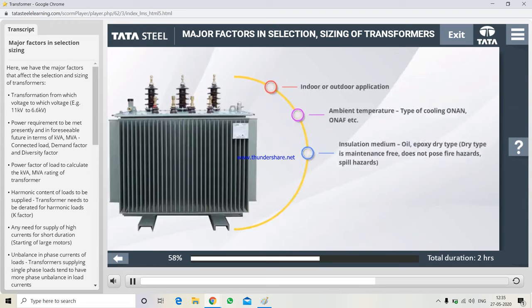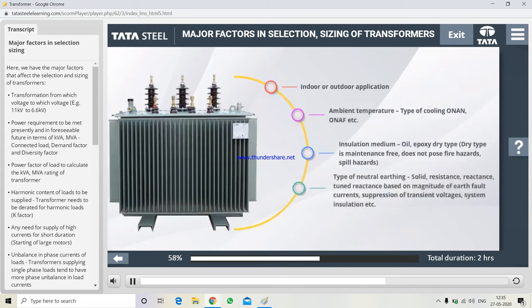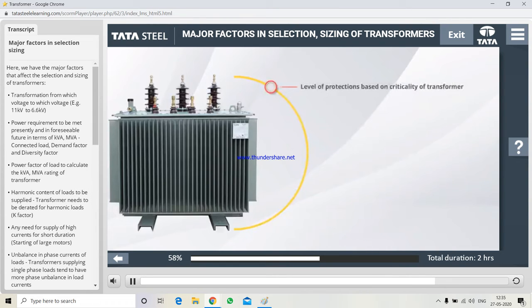Dry type is maintenance-free, does not pose fire hazards, spill hazards. Type of neutral earthing. Solid, resistance, reactance, tuned reactance based on magnitude of earth fault currents, suppression of transient voltages, system insulation, etc. Percentage impedance from the point of reducing fault levels. Higher percentage impedance reduces fault levels. Level of protections based on criticality of transformer.